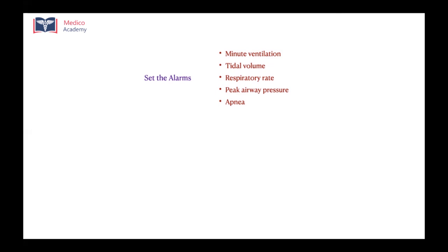There'll be alarms for peak airway pressures, because if you have a volume targeted mode where you have set the ventilator, you basically have no control over the pressure which is being generated in the airway. So you have to keep an alarm for peak airway pressure, so that you know that the airway pressures are going up, so that you can come and adjust the tidal volumes.